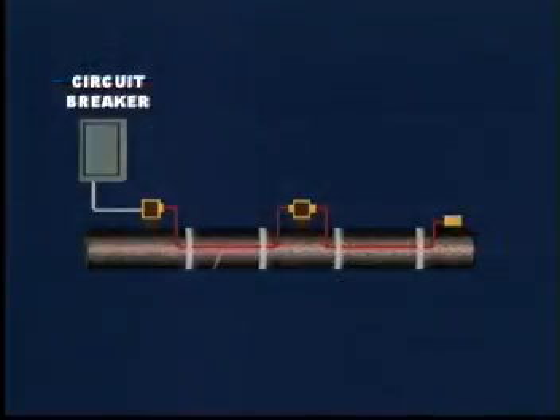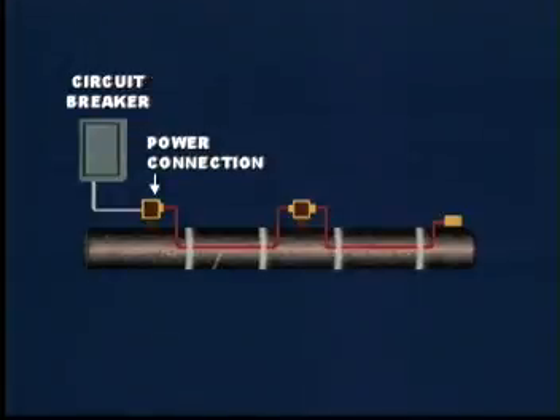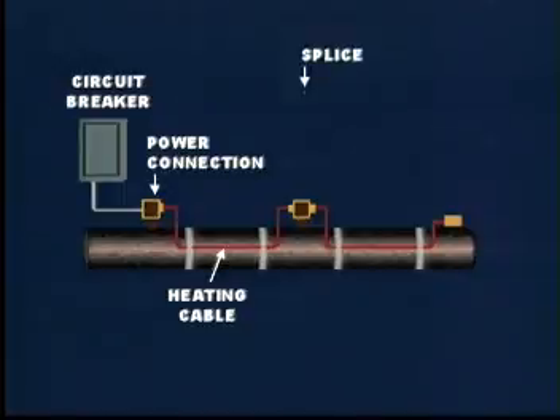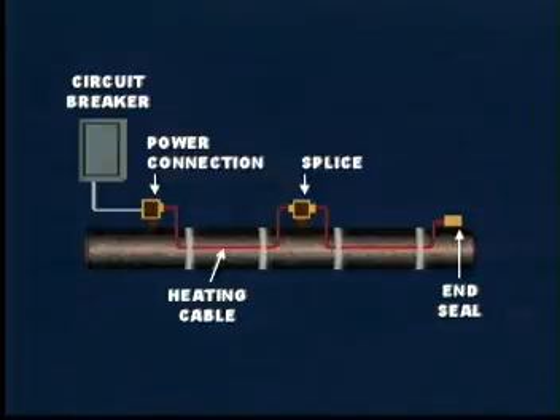This diagram shows how a typical heat tracing circuit is laid out on a section of pipe. Power is supplied through the power connection to the self-regulating heating cable that runs along the length of the pipe. The splices and tees are used to connect additional heating cables to the circuit. After the cable end is terminated with an end seal, the entire system is covered with thermal insulation.